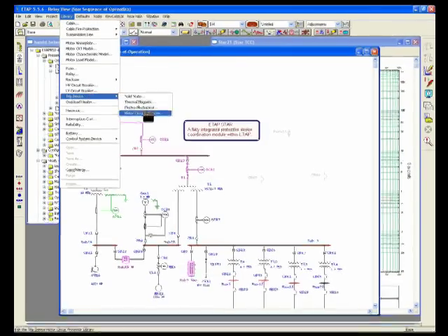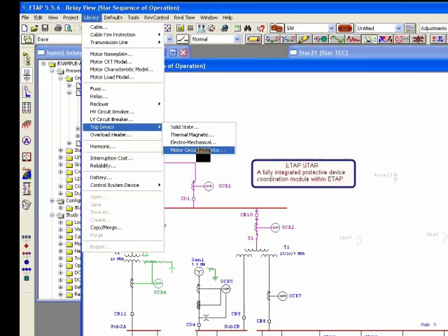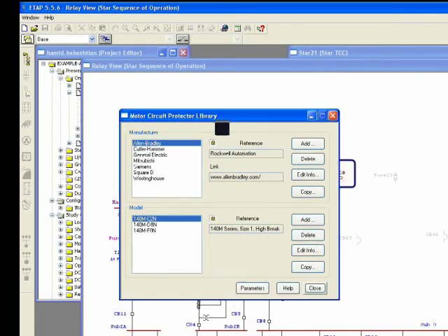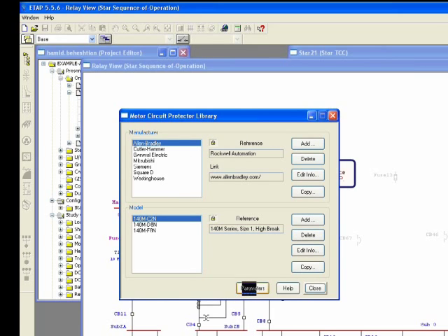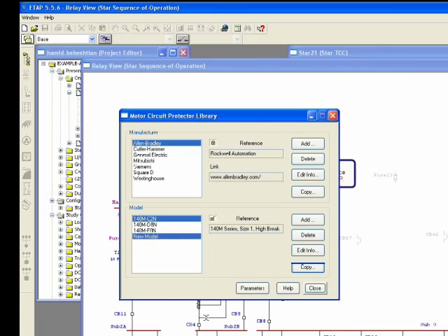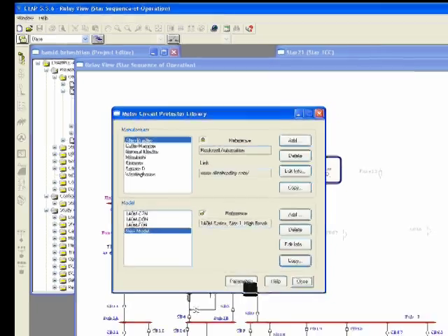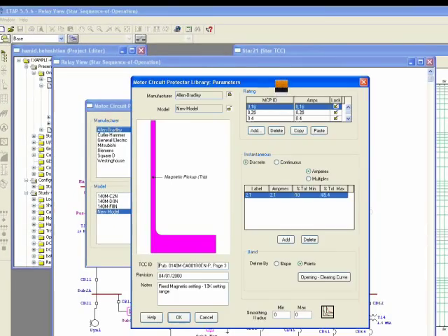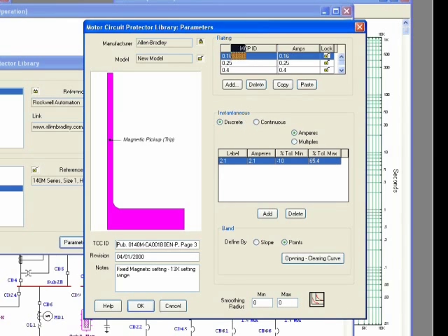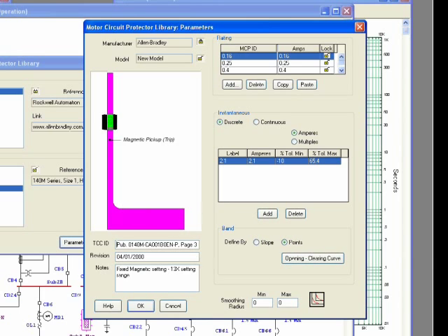The last item in the list for trip device is called MCP or Motor Circuit Protector. MCP is one of the simplest ones as far as the structure, because if you click on the parameter here, let me copy to the new model. So if I go to the parameter, I have only instantaneous pickup, simple as that, and you need to just specify the slope or the points for this portion.